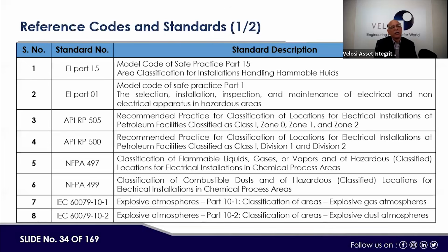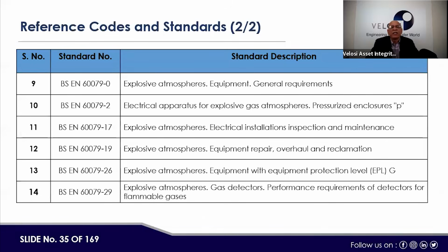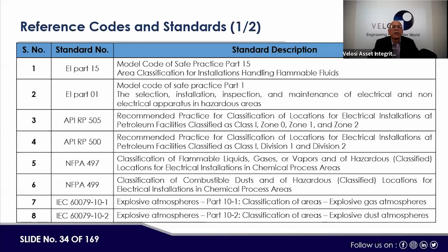Okay, now if we go to IEC 60079, Part 1 to other parts, till Part 29 and above, these are basically the standards. 60079 is for the selection of electrical equipment, or the explosion-protected equipment which could be installed inside the process facilities. If we say IP-15, it means Model Code of Safe Practice, Part 15: Area Classification for Installations Handling Flammable Fluids. Then Part 1 is selection, installation, inspection and maintenance of electrical and non-electrical apparatus in hazardous areas. So if Part 15 and Part 1 are combined, they cover both the hazard area classification process as well as the selection of E&I equipment. Then 505 is a recommended practice which uses basically the same terminology as IP-15. Then API RP 500 and other standards, right?